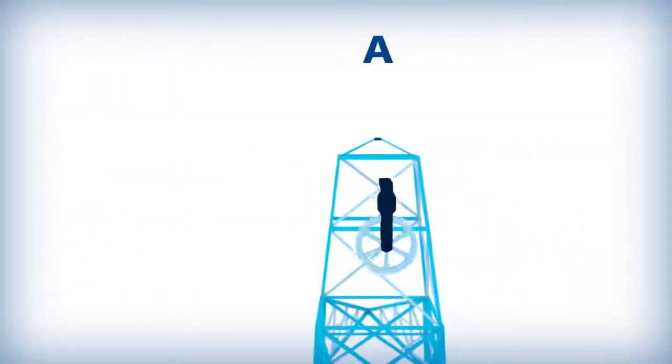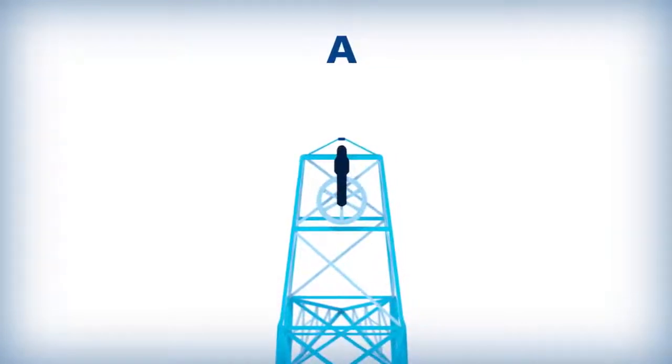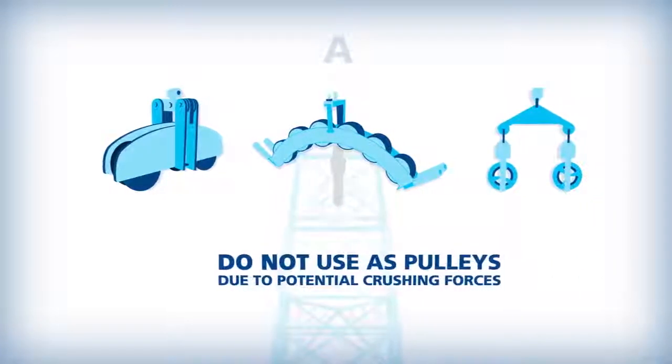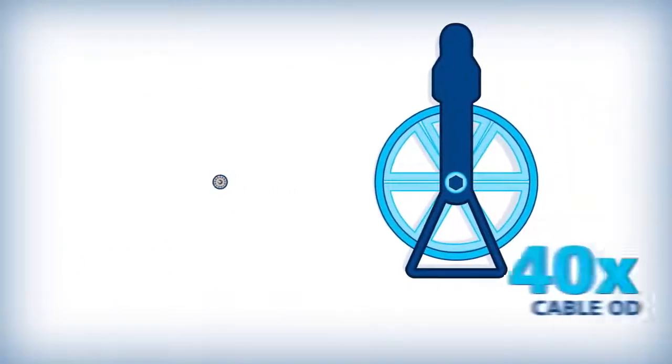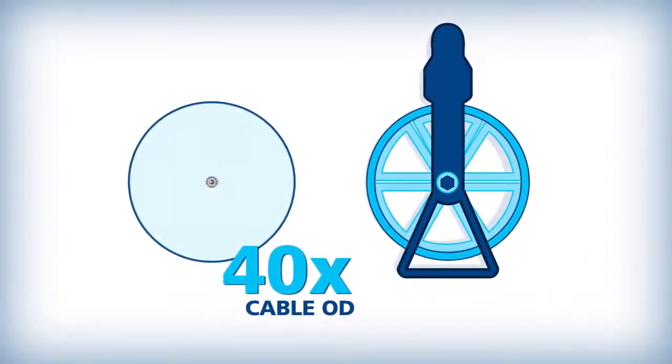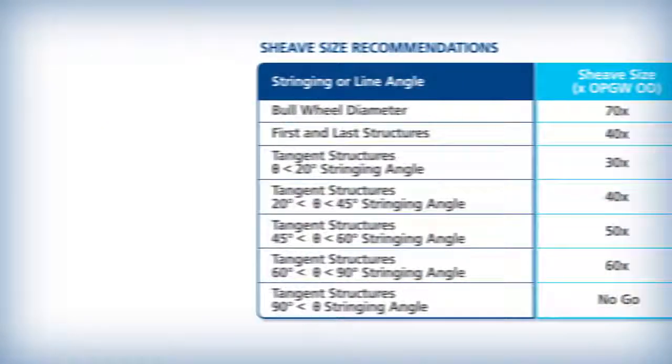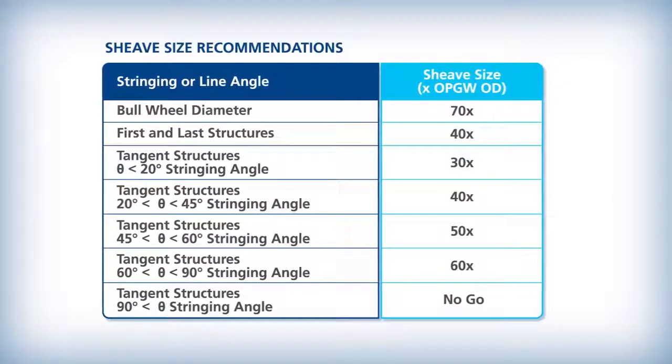Stringing blocks, or travelers, are mounted on the tower at the OPGW attachment point. Radius blocks, banana blocks, and array travelers should not be used as pulleys due to potential crushing forces. AFL recommends a pulley with a diameter of 40 times the cable outer diameter at the first and last structures. Straight pulls can use a pulley with a diameter of 30 times the cable outer diameter.